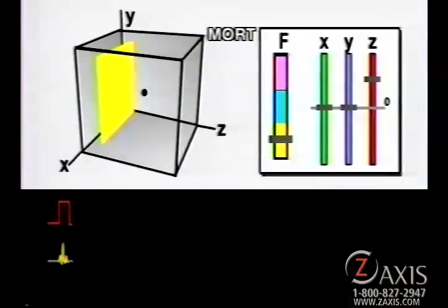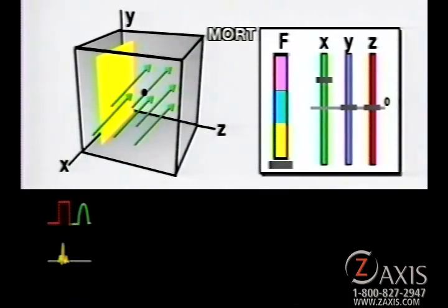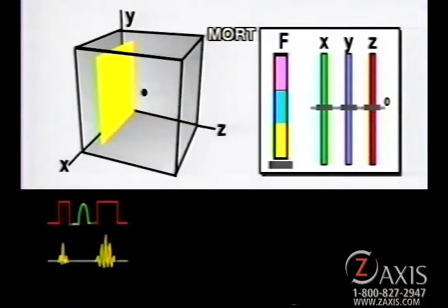In the multiple image orthogonal mode, or MORT, the gradient coils are again turned on individually, but different frequencies of RF are used to move the image plane through the scanning volume along a single axis.